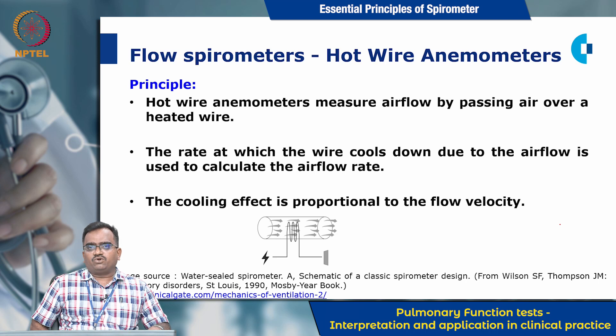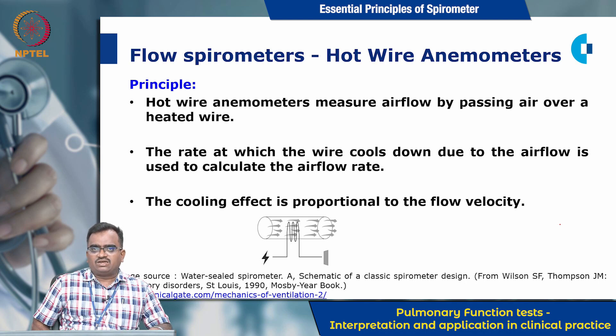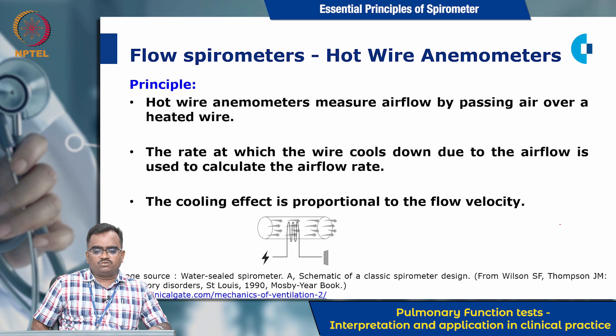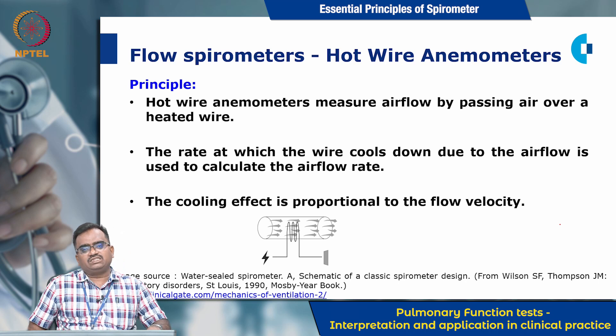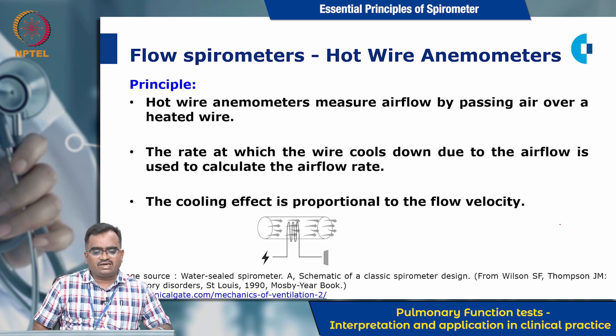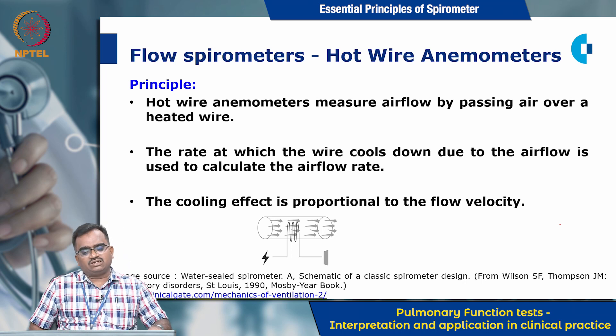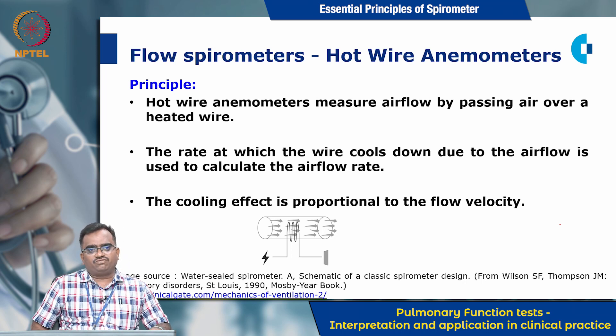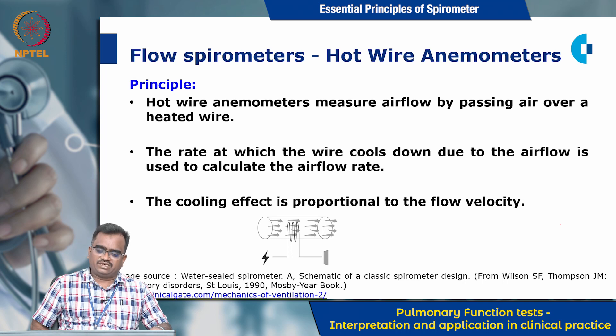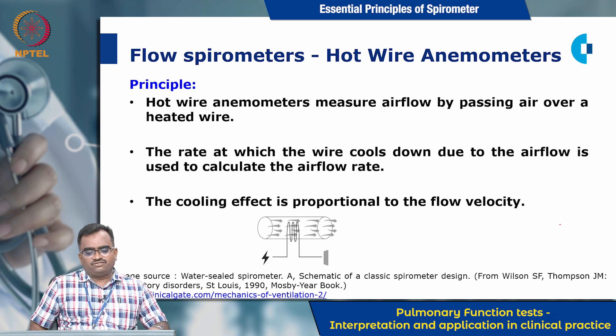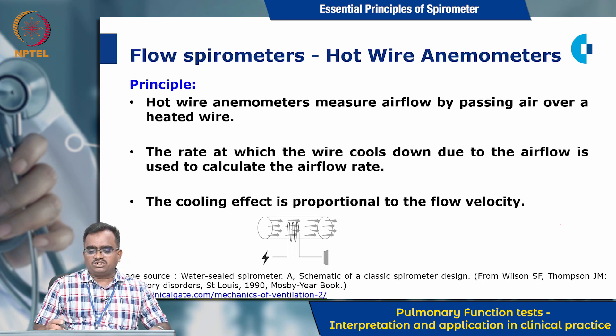The next type of flow spirometer is the hot wire anemometer. Here, the hot wire anemometer measures airflow by passing air over a heated wire. The rate at which the wire cools down due to airflow is used to calculate the airflow rate. The cooling effect is proportional to the flow velocity.